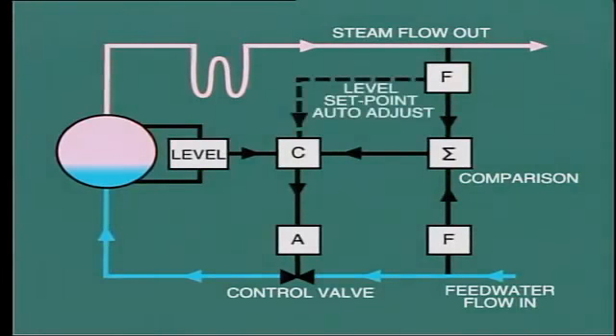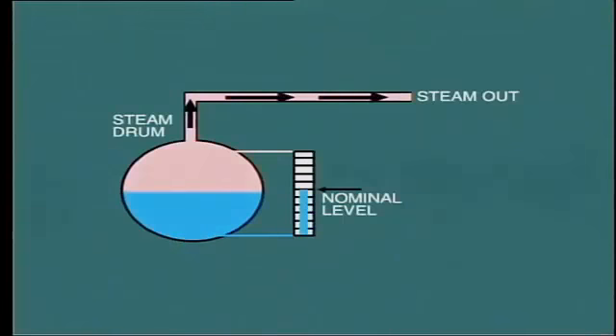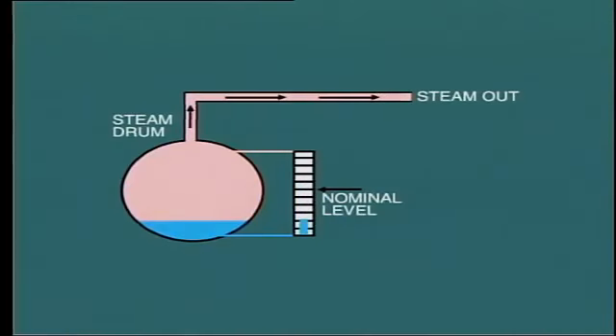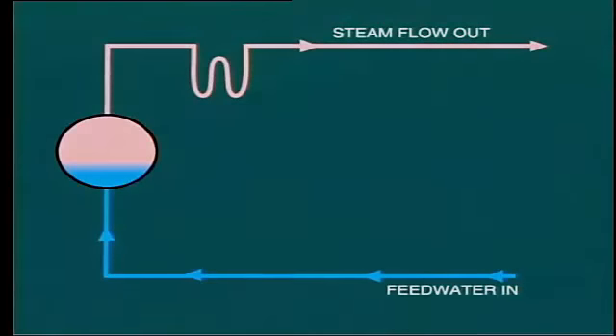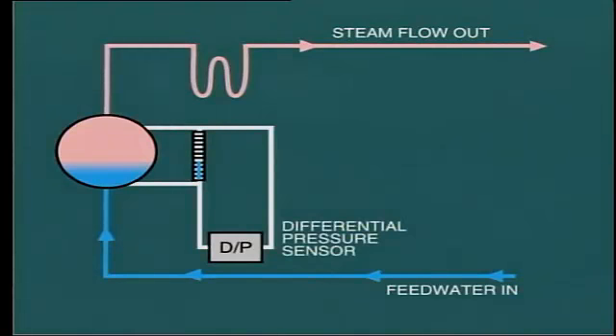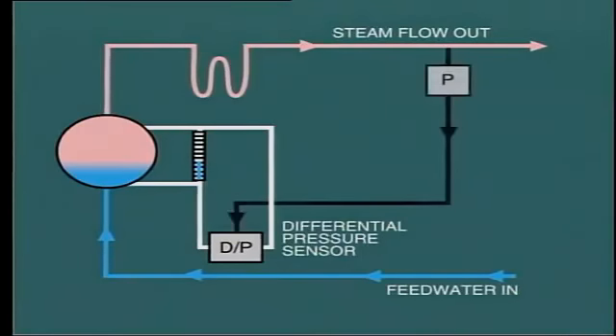In some control systems, the set point value of desired water level is automatically adjusted with load — that is, steam flow out of the boiler. At high load, the target level is maintained slightly higher in anticipation of a possible load rejection with consequent rapid fall in level due to shrinkage. Conversely, at low load, the set point is adjusted to maintain a slightly lower level in the drum, anticipating the possibility of a sudden increase in steam demand with resultant increase in water level. A further refinement concerns the mode of measuring water level, which is usually inferred from the pressure indicated at the bottom of the column of water. The density of water in the drum changes with saturation temperature and therefore pressure, so the drum level measurement is corrected for pressure variation by adding a pressure signal to the computation.